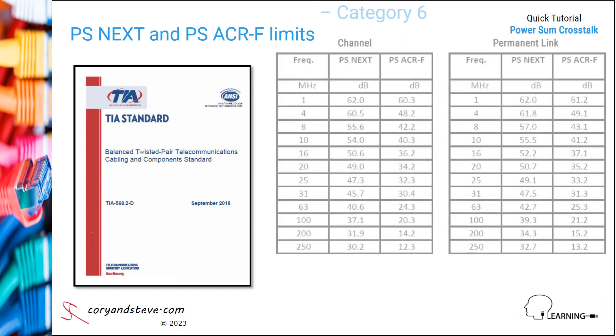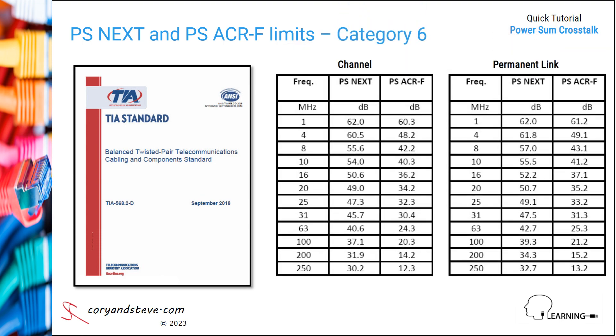Here are the limits for category 6, which is characterized to 250 megahertz versus 100 megahertz for Cat5E. The limits at a given frequency up to 100 megahertz are higher for Cat6 than for Cat5E, due to the better performance of the cables, connectors, and cords.